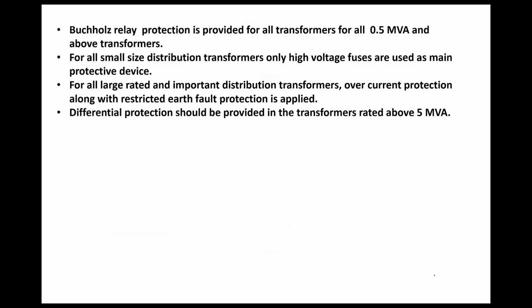Okay, some salient points which I have collected. Buchholz relay is used in all transformers above 500 kVA. Even nowadays they are using it for 250 kVA transformers, but mainly any transformer above 500 kVA will have a Buchholz relay.